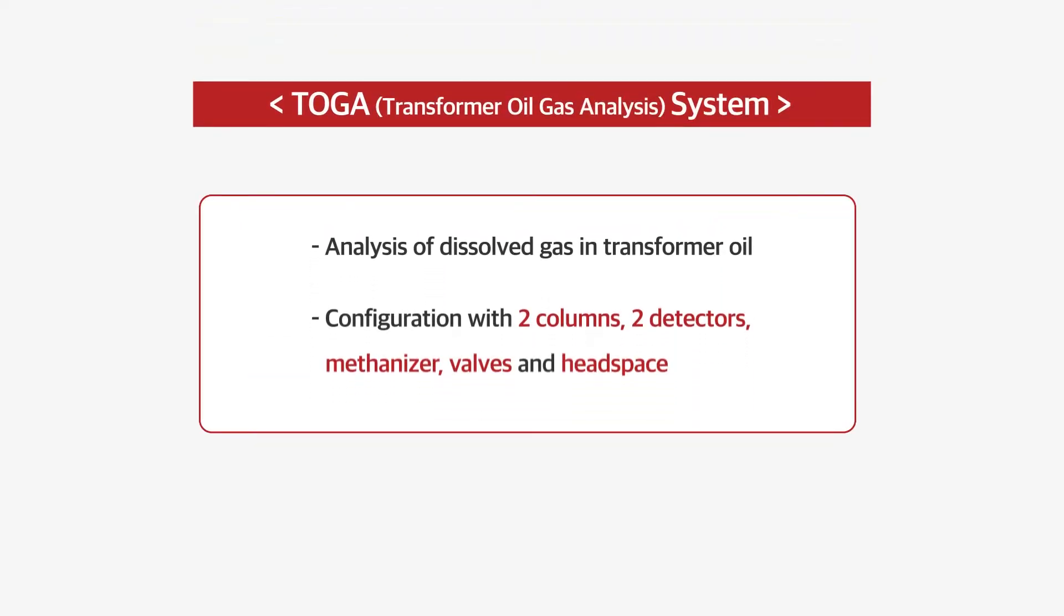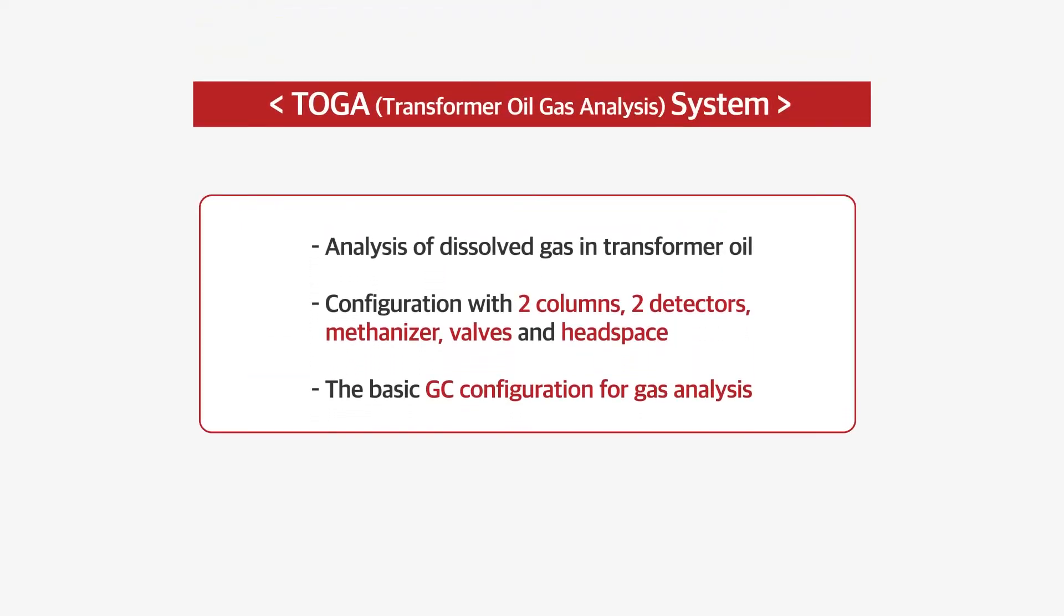TOGA system is for analysis of dissolved gas in transformer oil, in which the sample contains permanent gases and light hydrocarbons that cannot be analyzed with a single column and detector. This system is configured with two columns, two detectors, methanizer, valves and headspace, so it is widely referred to as the standard of gas analysis.